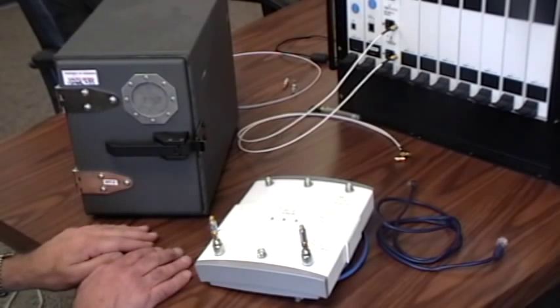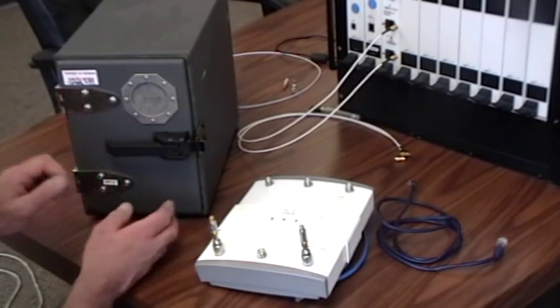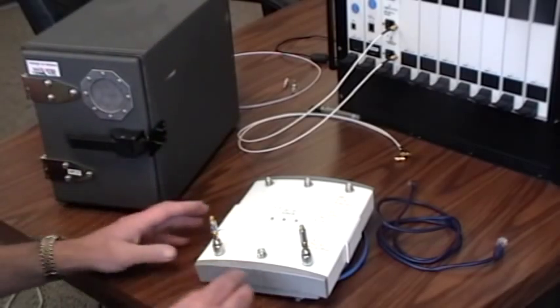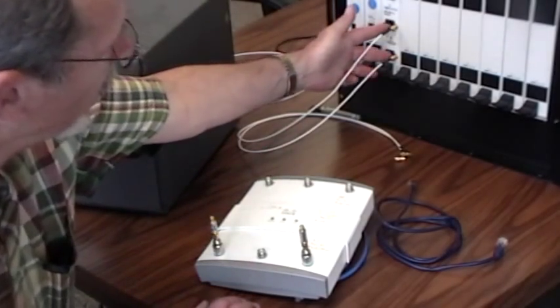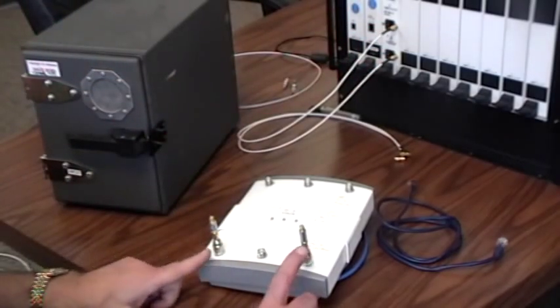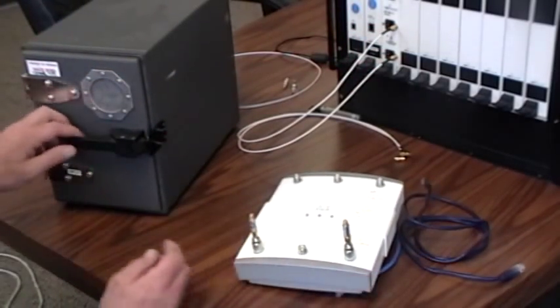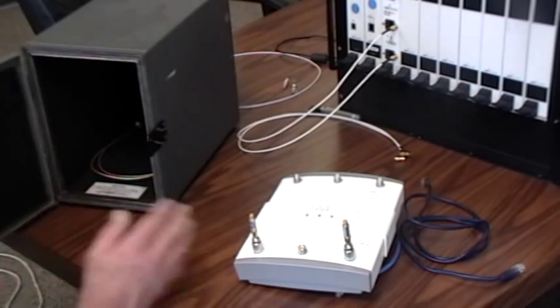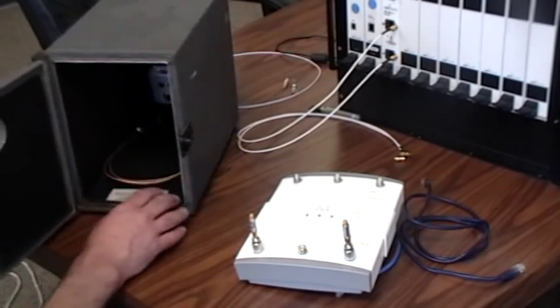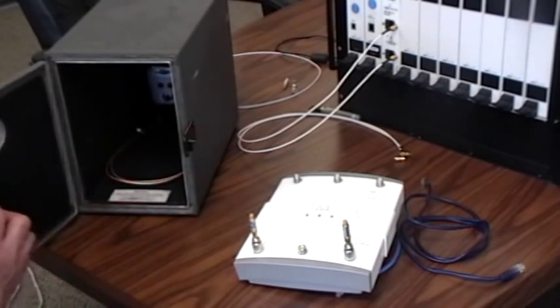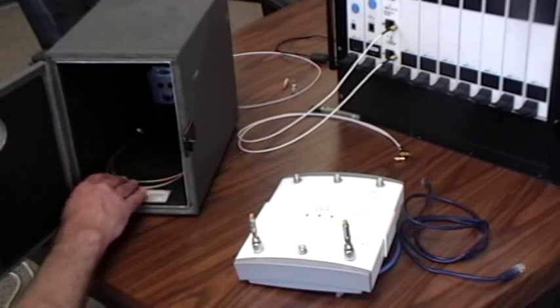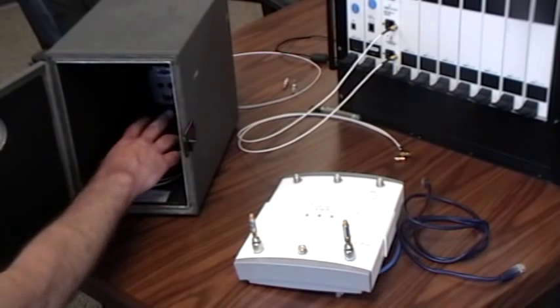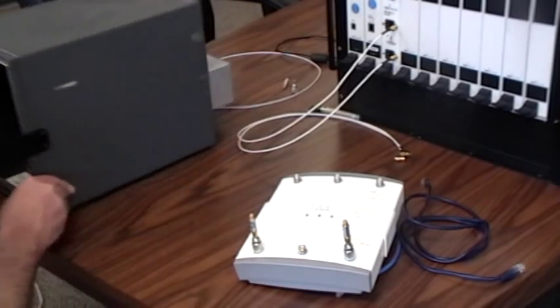We're going to go through the steps to put this access point inside the RF enclosure. We're making the exact same connections, port A and port B of our wave blade to port A and port B on our access point, except the access point will be inside an RF enclosure. We have a fairly straightforward RF enclosure. I've already connected cables to the bulkheads inside. We're going to show you what that looks like from the back side.